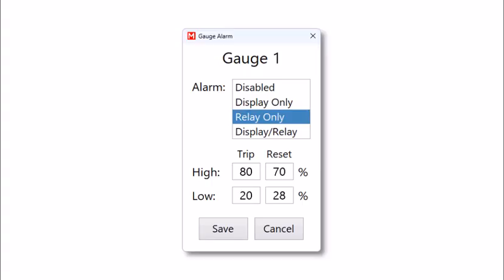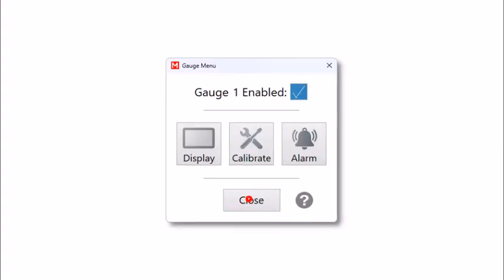selecting the Relay Alarm option will enable the pin for this port to send an alarm signal to an external system. Examples can include a 120-volt AC lamp or audible alarm speaker, a motor starter for an auger, a relay that will serve as an external command to a dryer system, or a command to another existing automation system. For more information on how to set up these circuits, please refer to your user manual and contact MTEC with any questions. After making any desired changes to your alarm setup, select Save and then return to the main screen.